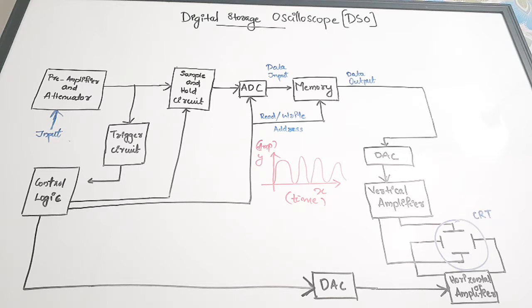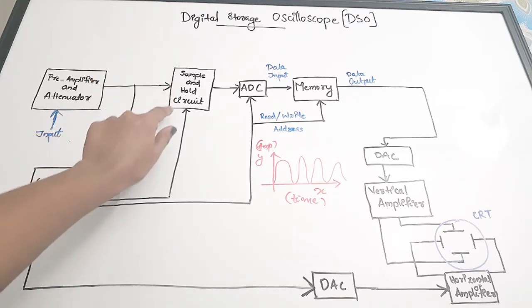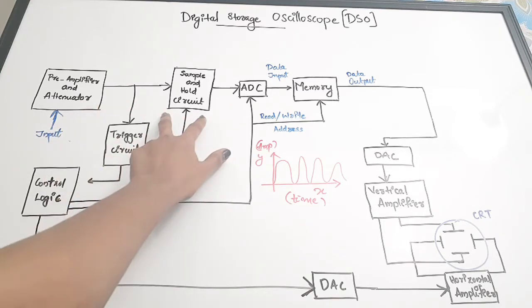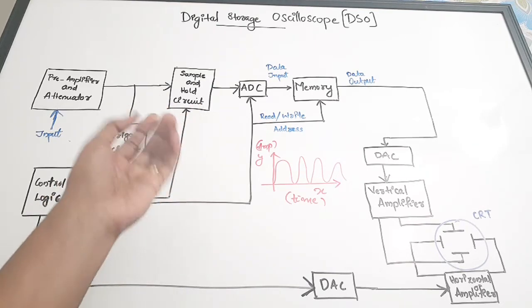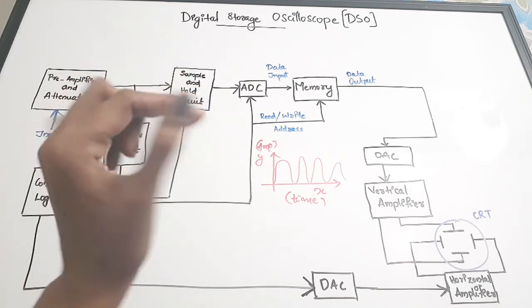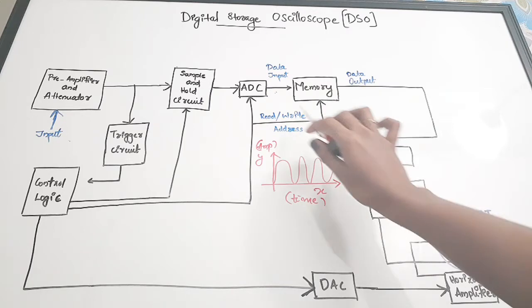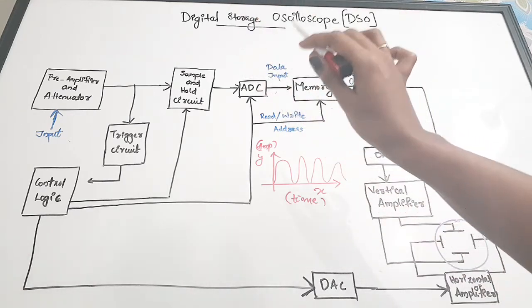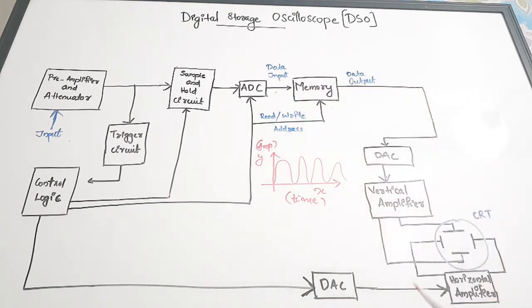For the purpose of digitization, the next unit is a sample and hold circuit. Sampling is the basic process of digitization. The signal which is in analog format is sampled with the help of a sample and hold circuit, and then it is fed to an ADC. The ADC converts it to digital format, so we get digital data at this point. It is then given to a memory unit, and hence the digital data gets stored in memory - that is why we call it a digital storage oscilloscope.